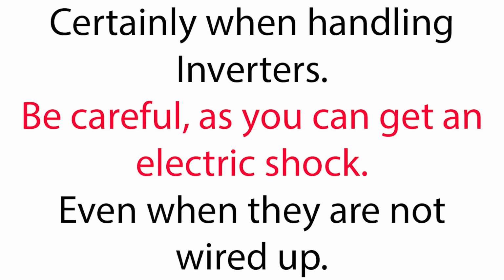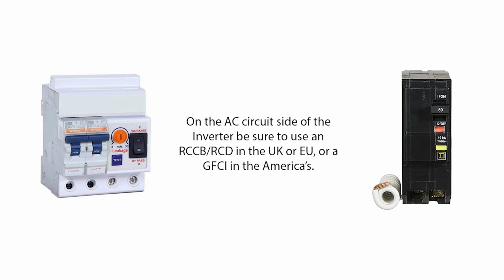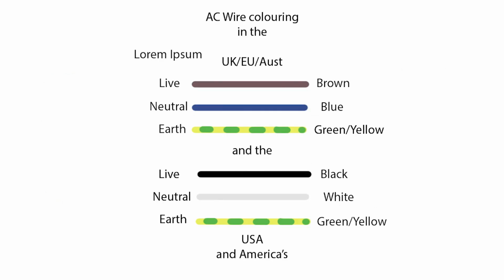Last thing, just because you are using 12 volt battery power, don't be thinking you can't get an electric shock. The inverter may still retain the capability of giving a nasty, if not fatal, electric shock, even when it's turned off. Protection against an AC electric shock is the job of the leakage current breaker. In my case, with my 1000 watt inverter, I'm in the UK, so I use a 230 volt 10 amp RCCB, which stands for Residual Current Circuit Breaker, with overcurrent and shock protection, installed within a consumer unit housing to reduce electric shocks and keep everything in the AC circuit running safely. In the USA, where most residential appliances run at 110 volts, a voltage leakage current breaker would be referred to as a GFCI, or a ground fault circuit breaker. You can use a single or a dual pole circuit breaker. If you do use a single pole breaker, just be sure to wire it to the live brown cable wire in the UK or the black cable wire in the USA.